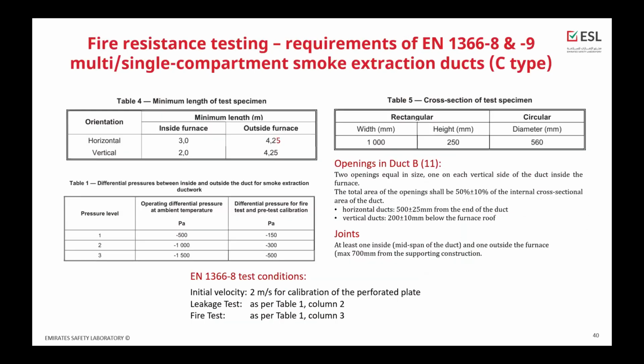If we are talking about smoke extraction ducts, either multi or single compartment, we are basically talking about the same construction. The length of the duct inside the furnace should be at least 3 meters. Outside the furnace, at least 4.25. Why is there 0.25? Because 250 millimeters away from the wall, we need to place the perforated plate, which helps us to make underpressure inside the duct.